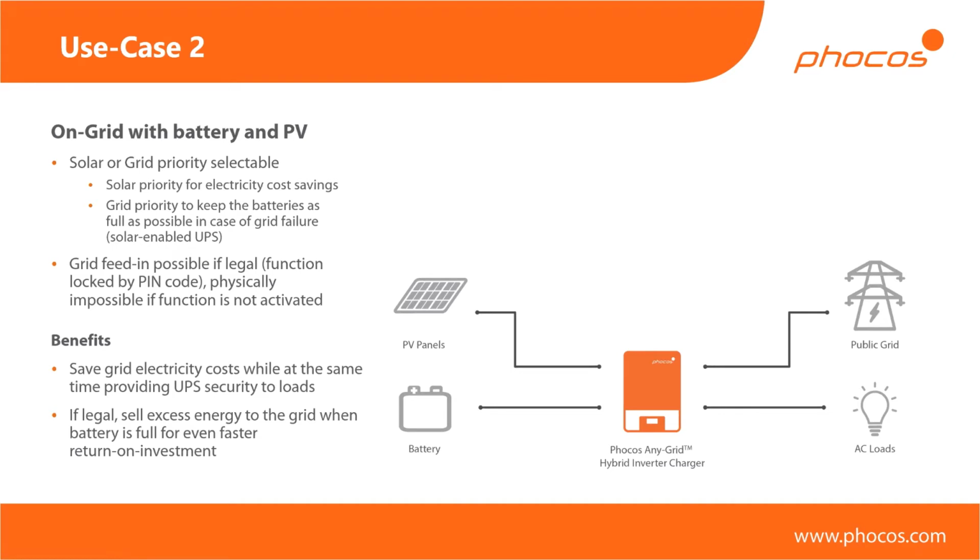People get frustrated because they've invested into PV modules and a battery, which are basically the two critical components along with the inverter. But if the grid fails, they're still sitting in the dark, even though their battery might be full and the sun might be shining, or just one of the other. So in this case, that's just not going to happen, because if the grid fails, that's fine. The inverter's simply working in off-grid mode.